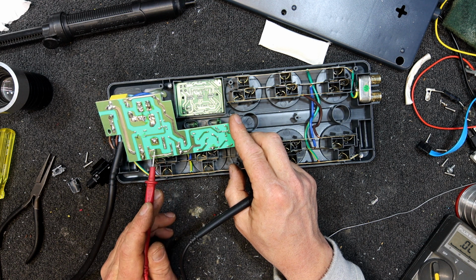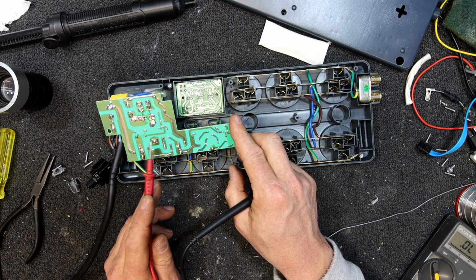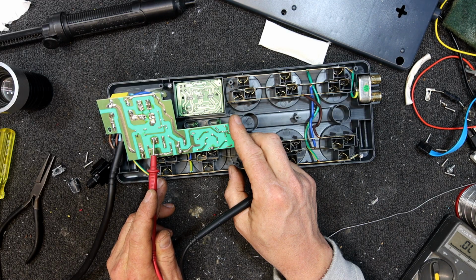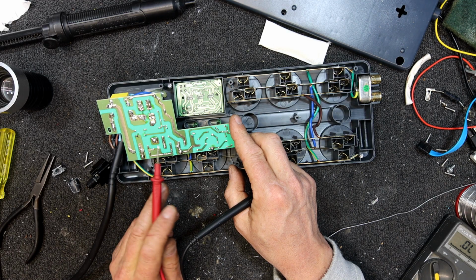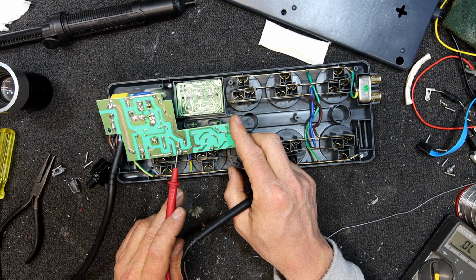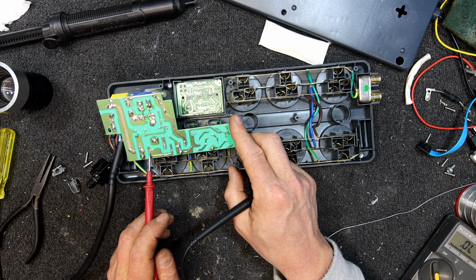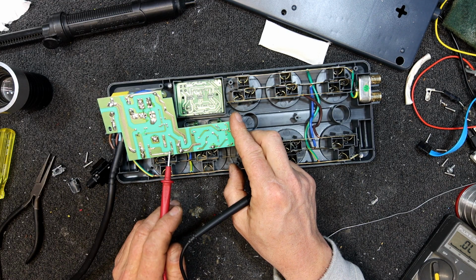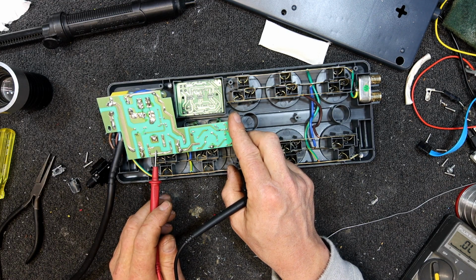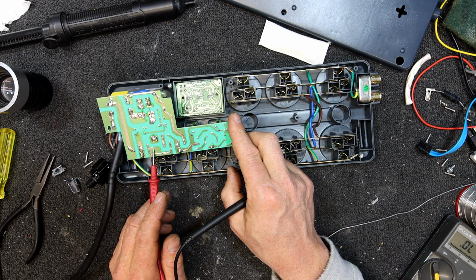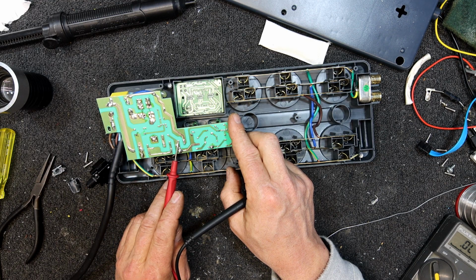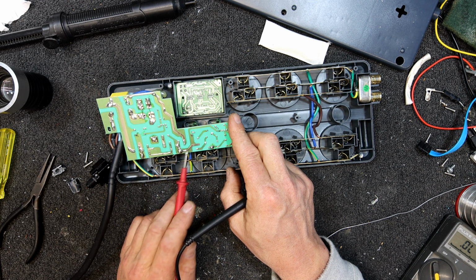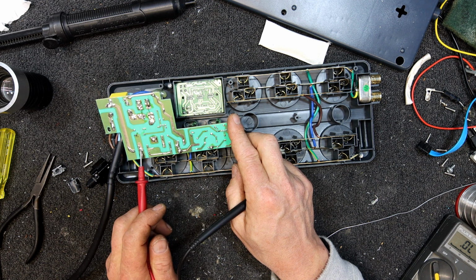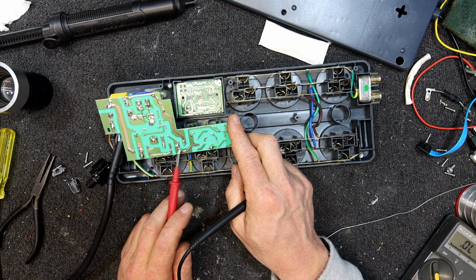So this just has a slightly different path to ground, including a fuse and a gas discharge device. But if a surge hits this thing, either the neutral side or the active side is going to be shorted to ground. These metal oxide varistors will go low value. They basically liquefy inside, if I remember rightly, which turns them into just like liquid metal, I guess. Low resistance. It's going to blow that thermal fuse or that thermal fuse. If you get a bad one, it'll probably blow both of them straight away. So I guess these are similar to a TV or something that's got one fuse.